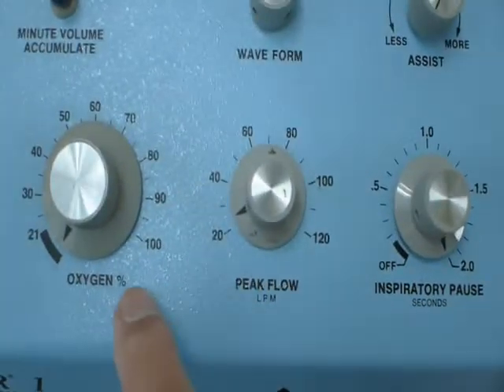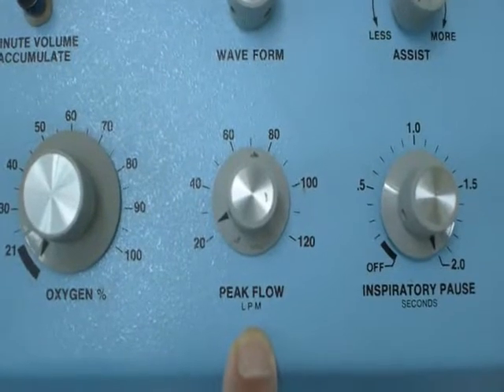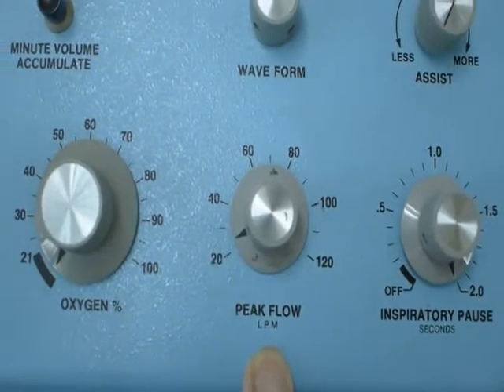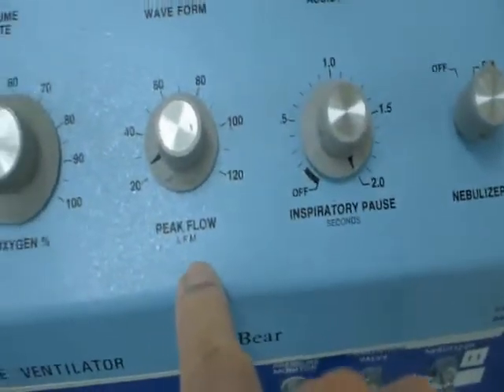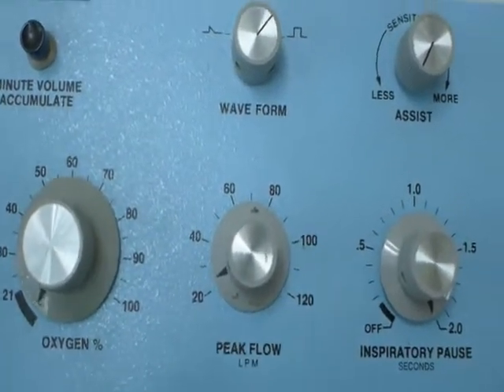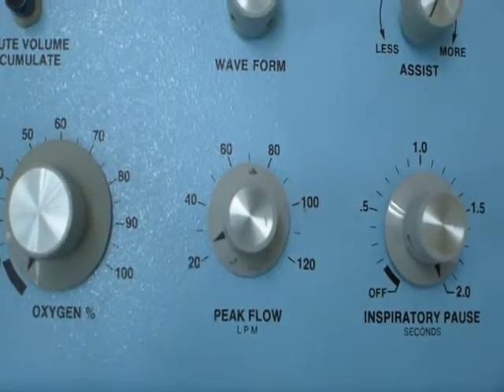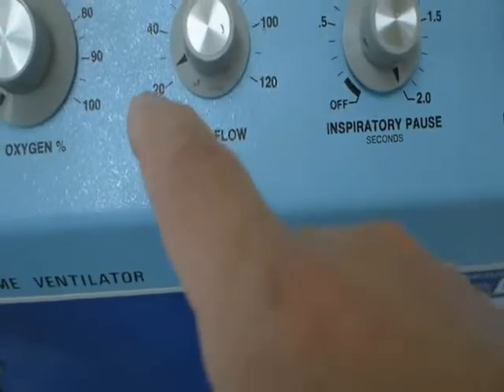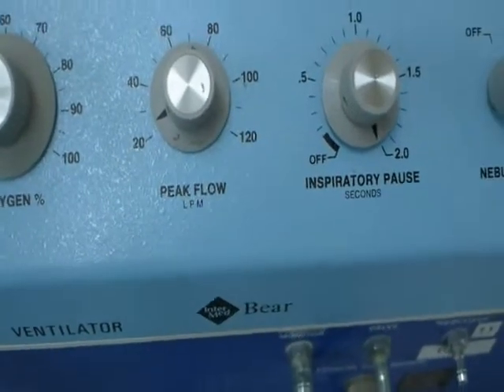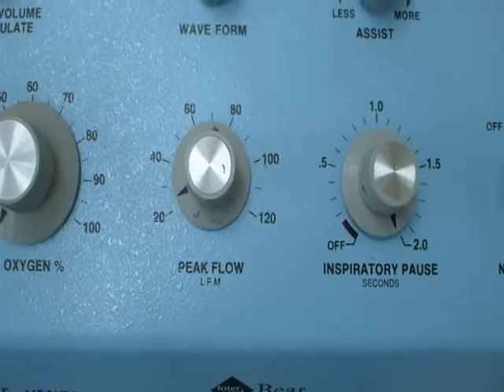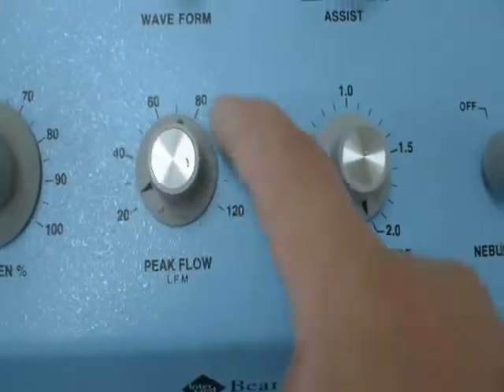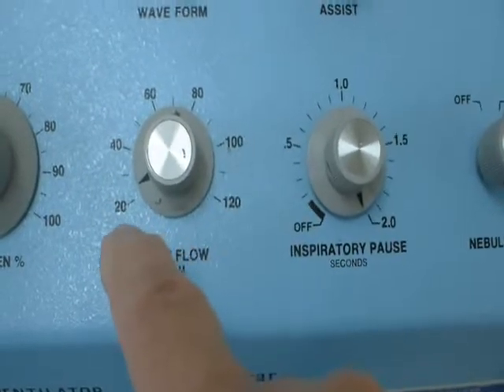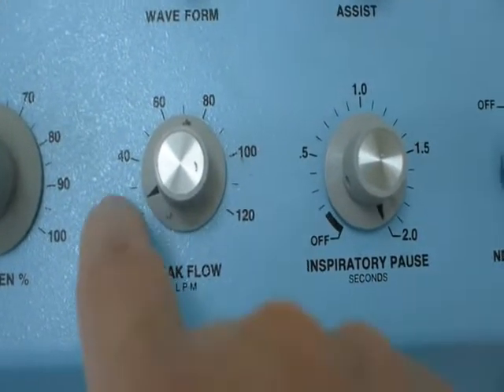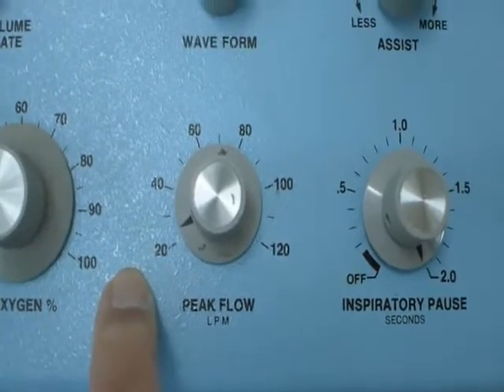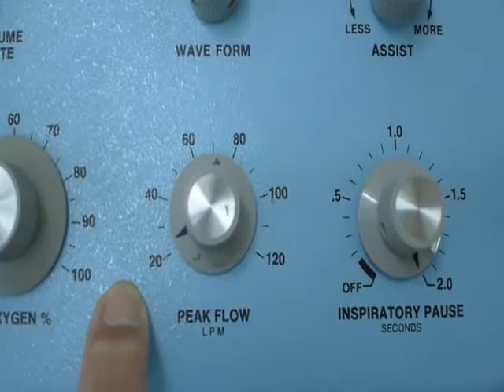Okay. Now we'll go back to this control here. We have a peak flow. The peak flow is the amount of flow that we want to give to the patient in one minute. So how many liters it is sending to the lung is pretty fast. It doesn't mean that the patient is going to get the whole 20 liters in one shot. No, it has to be divided by the respiration rate also, so that it will continue giving to the patient. This peak flow will affect the waveform of the gas that is pushing the gas to the lungs of the patient.